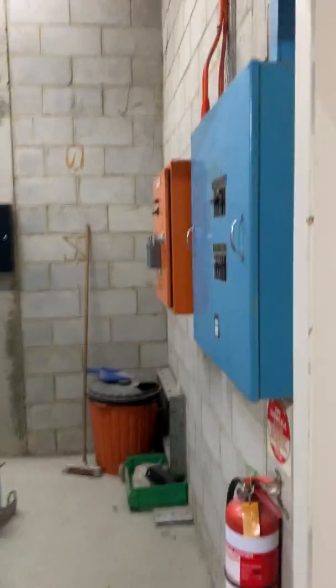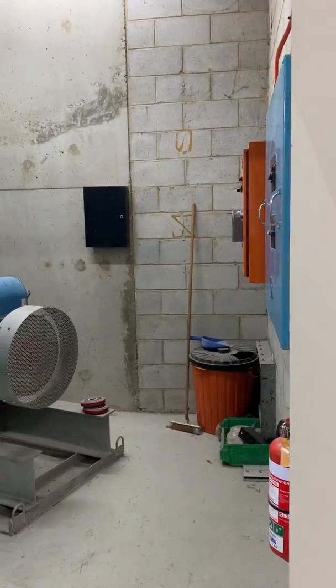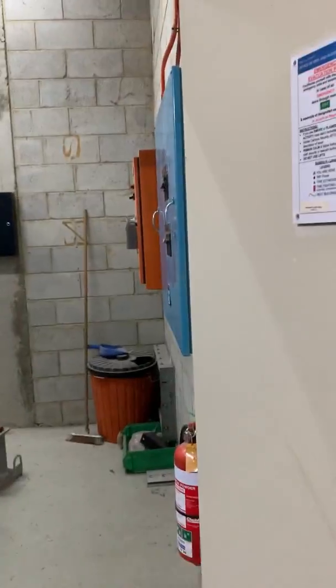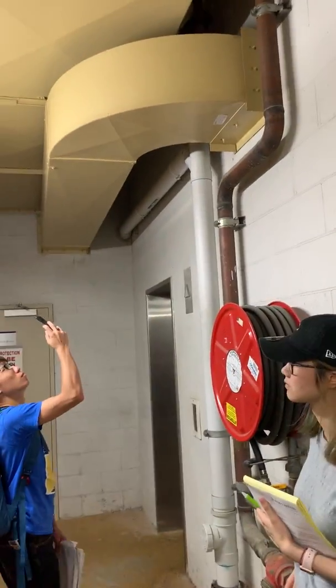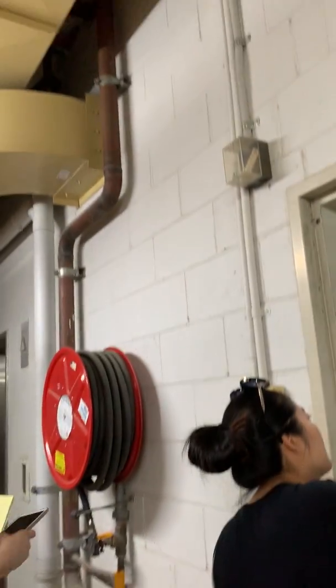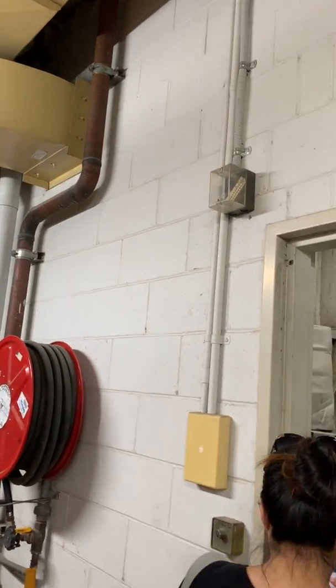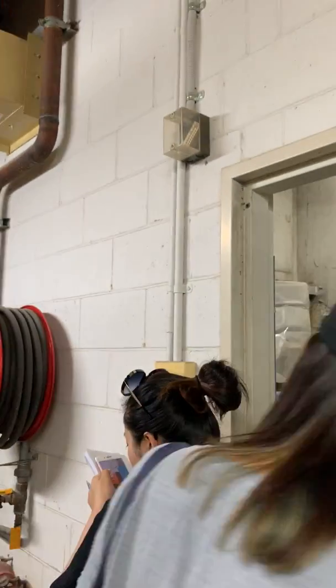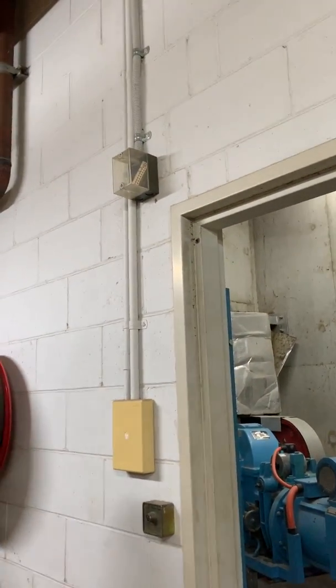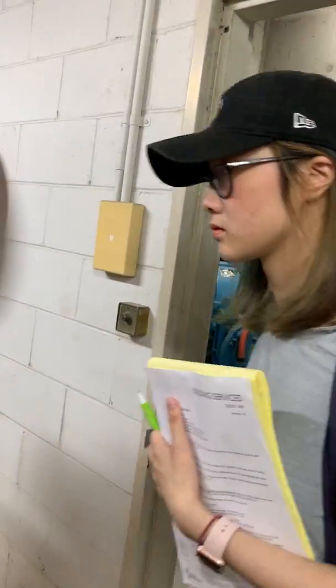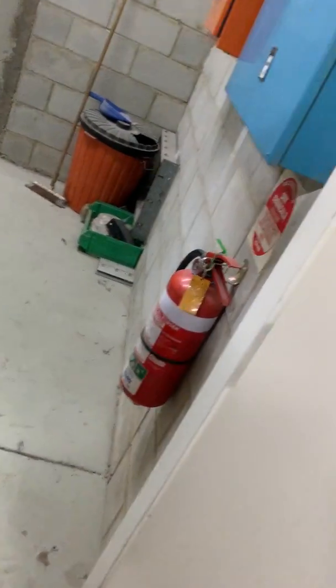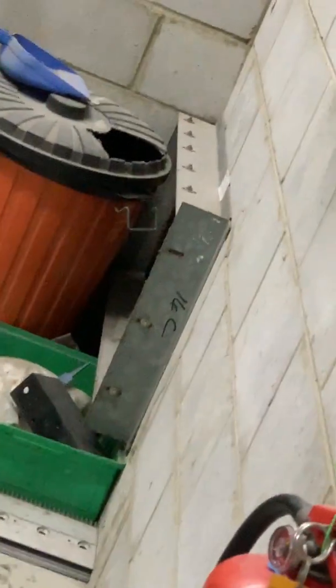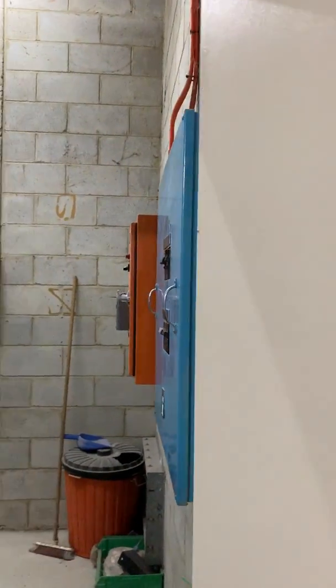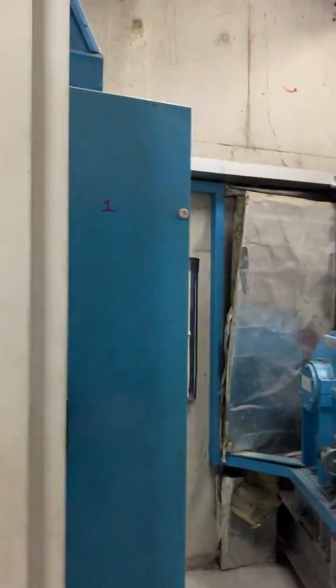And the orange panel is the control of the exhaust. So you can see this small duct coming out of the wall there. There's an exhaust point in the wall inside this room drawing hot air out. You can imagine if that motor's running a lot, it's going to get quite hot in there. And there is an opening down the bottom which is drawing in cooler air. The blue panel that you saw just to the left of the door, that's the control panel. So when you press the button, that turns on.